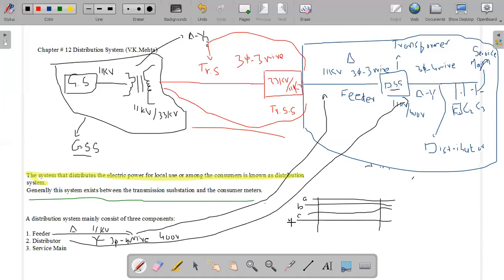The reason for connecting the distributor in Y configuration, without earthing the neutral but having a neutral wire, is that if you want 220 volts — a single phase connection — you can simply take it from a single phase, say phase C, and a neutral. Here the phase voltage will be 220 volts, and this connection is known as a single phase connection.